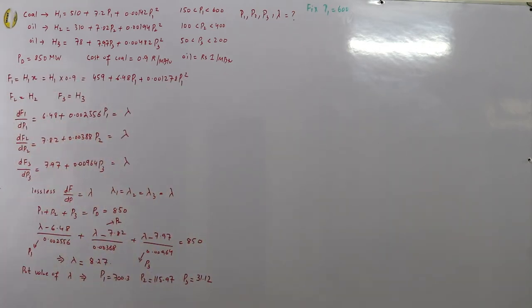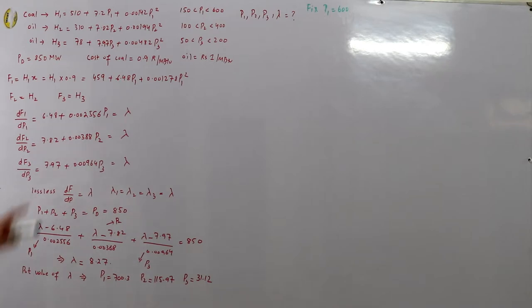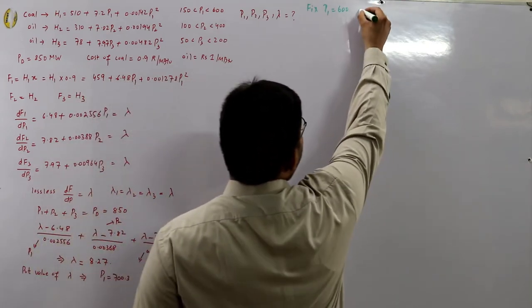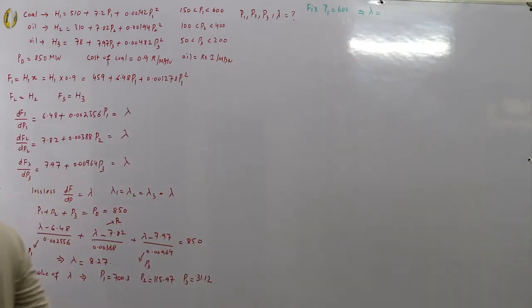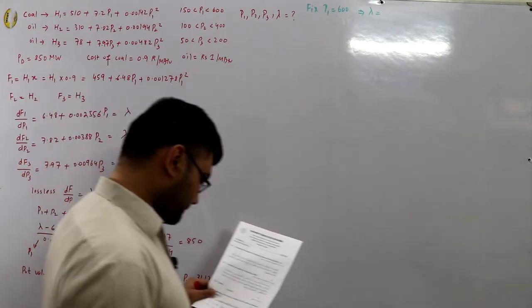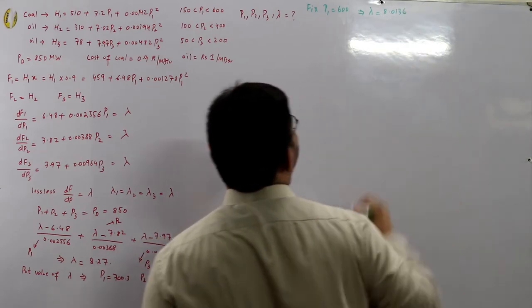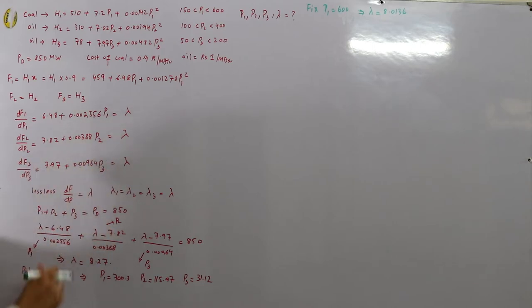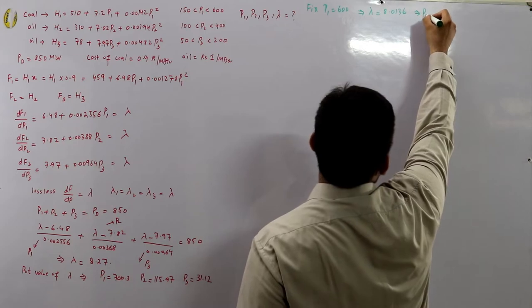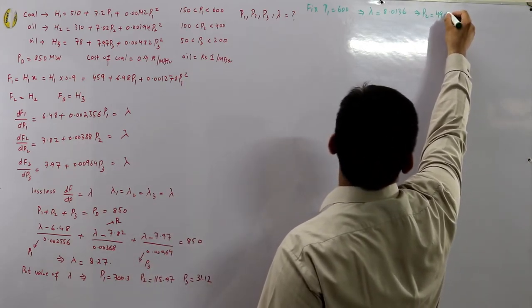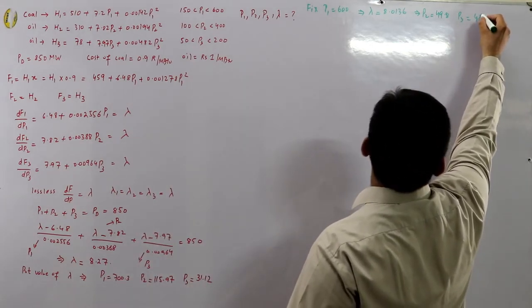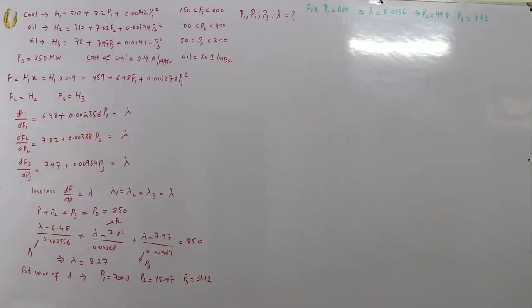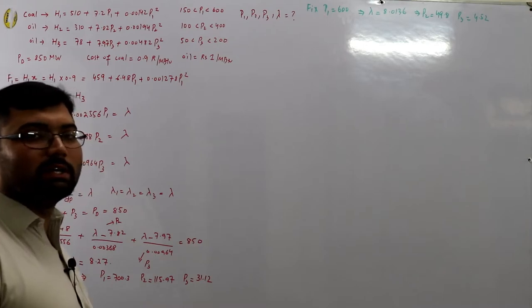With p1 fixed at 600 MW, find λ from the df1/dp1 equation: λ = 8.0136. Substituting this into the p2 and p3 expressions gives p2 = 449.8 MW and p3 = 4.52 MW — p3 is still below its minimum of 50 MW, so we've missed again.